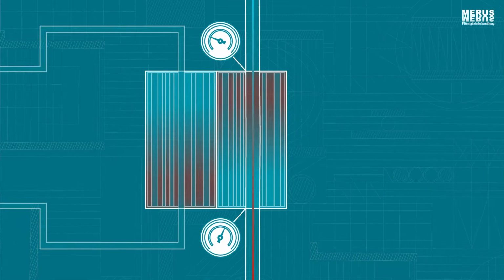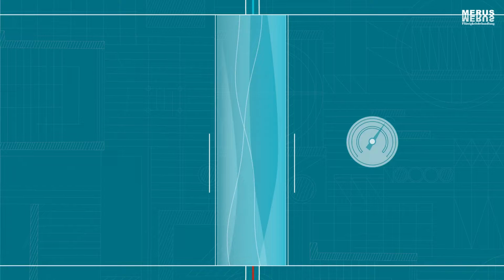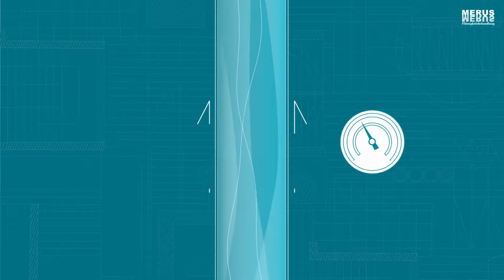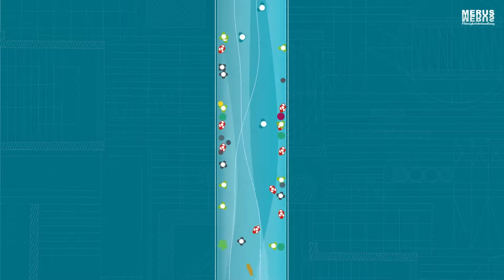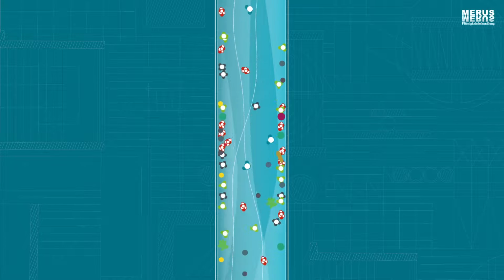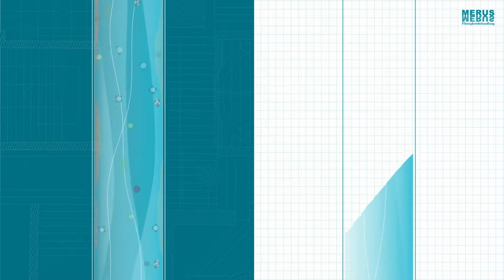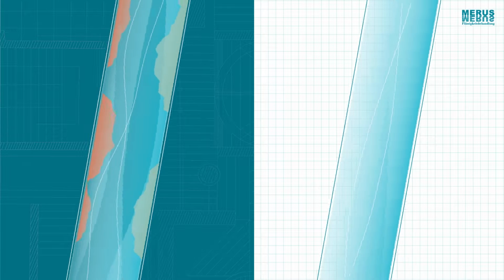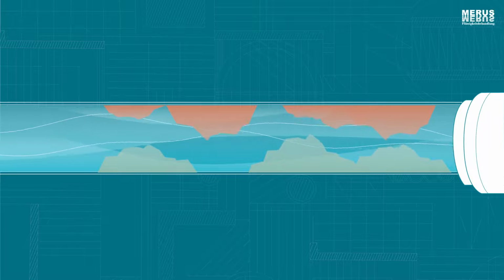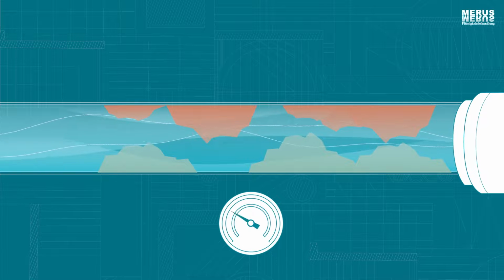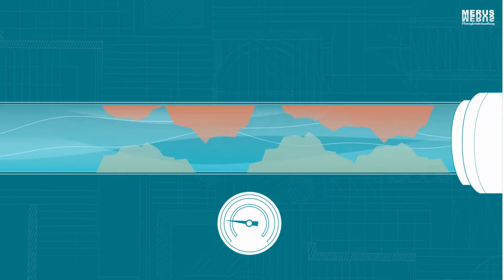On its way through the heat exchanger, the water pressure decreases due to the friction of the water on the inner wall of the pipe. With increasing deposits of limescale and other foreign substances, the friction is even higher than on clean pipes. In addition, the pipe's diameter is decreased by the buildup of deposits. A smaller diameter reduces the pressure at the heat exchanger's outlet further.